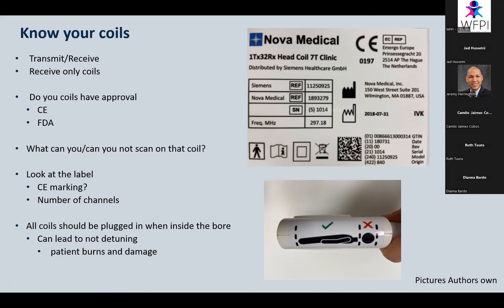If a coil is on a patient inside the bore but is not plugged in, it will not detune, which can lead to patient burns and coil damage. If a coil is on the patient and not being used, remove it. If you want to use it, it must be plugged in, or you won't get any images.